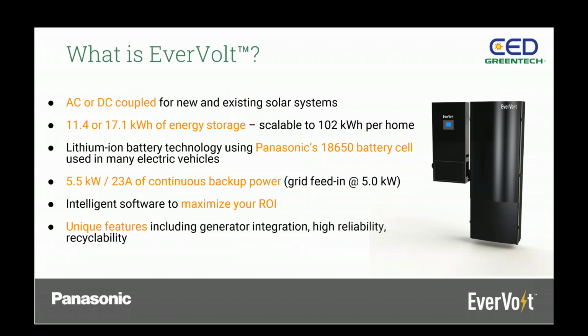So this is just summarizing again, it's AC or DC, and then we have 5.5 kilowatts and 23 amps of continuous backup from a single system. That's an EverVolt Plus. Now, it is important to note that the actual grid feed-in is 5 kilowatts. So there are certain programs out there that you have to stay under the 10 kilowatt feed-in limit to the utility grid.